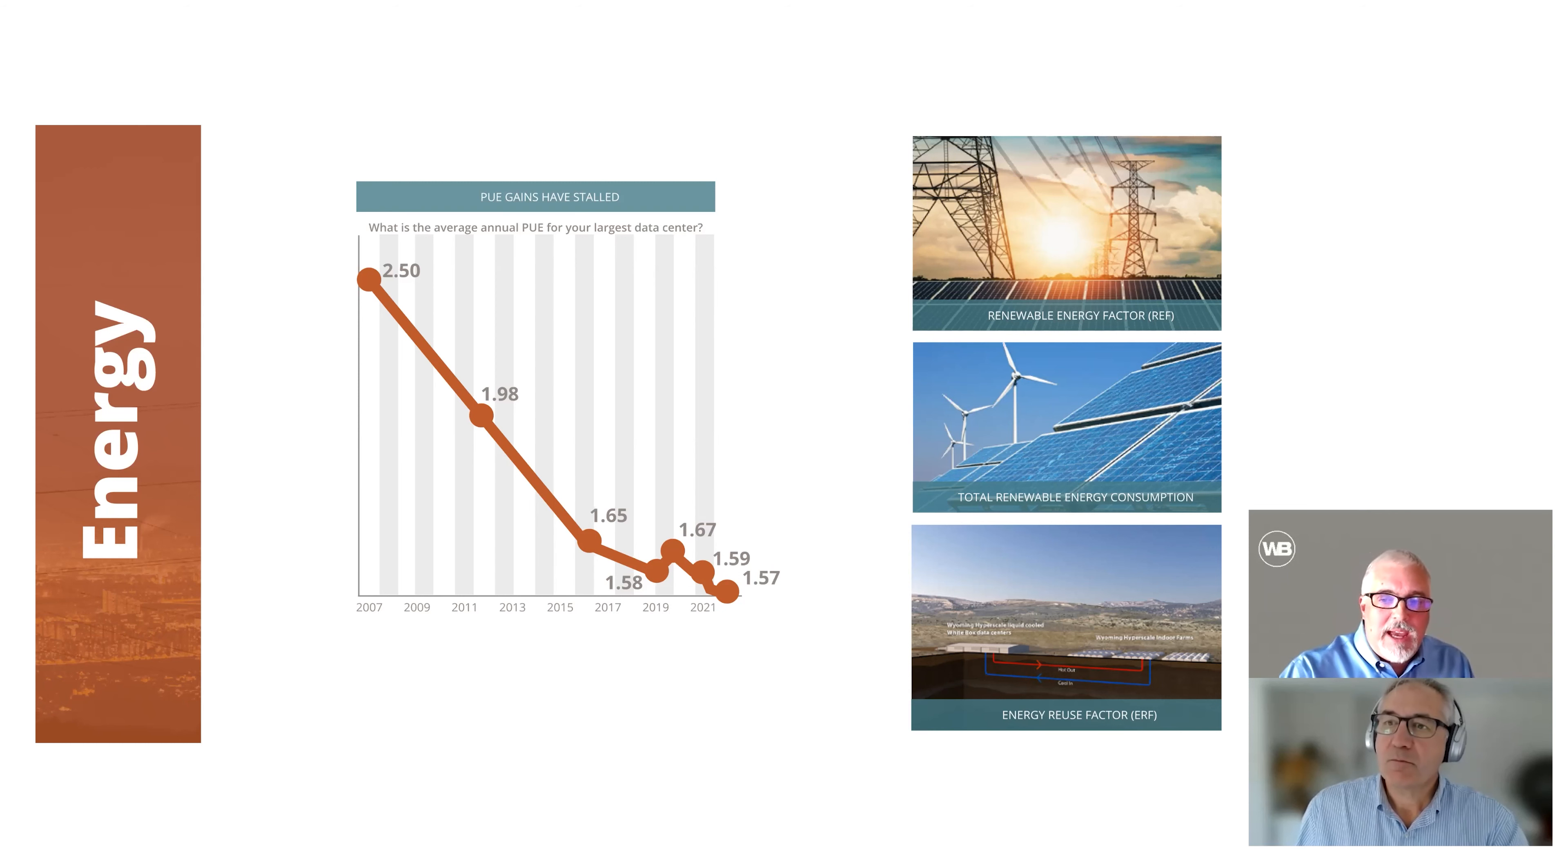So we look at how much total energy, how much renewable energy are you using? There's a renewable energy factor. Basically, it's from zero to 1.0. It's pretty simple. If you're using no renewable energy at your place, you're a zero. If you're using 100%, you're a 1.0. So anywhere in the range there is what we're starting to see more and people look at that.